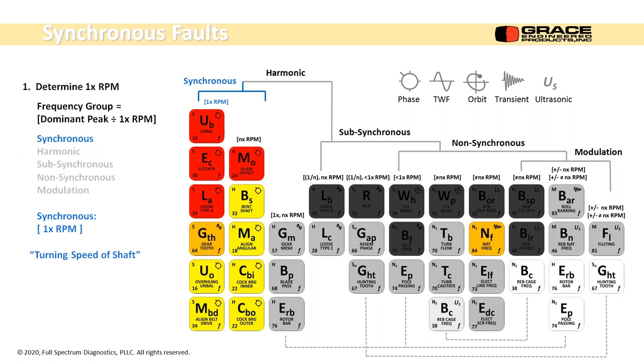The various components: synchronous is 1 times RPM, or the turning speed of the shaft. The rotating speed of the motor and pump and what have you. That's 1 times RPM. Everything in these two columns produces a 1 times RPM. They're very similar. This is the only one little oddball. This is going to appear everywhere.